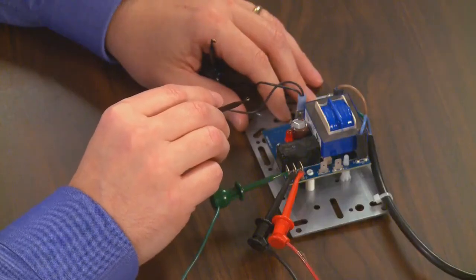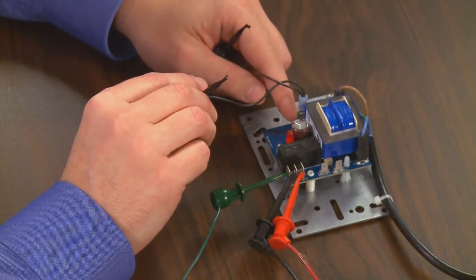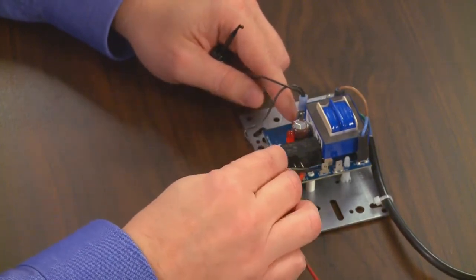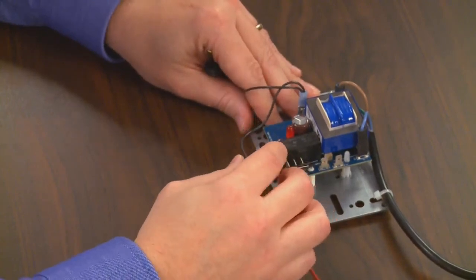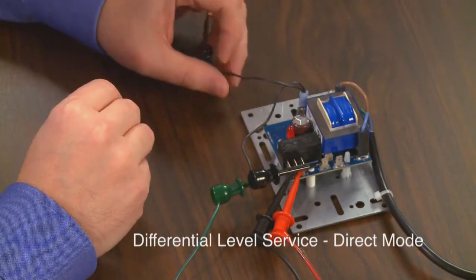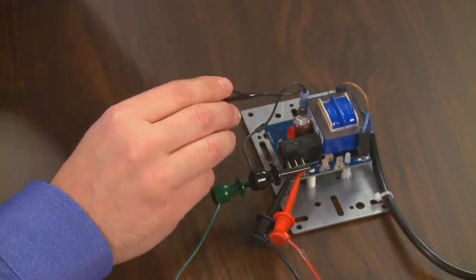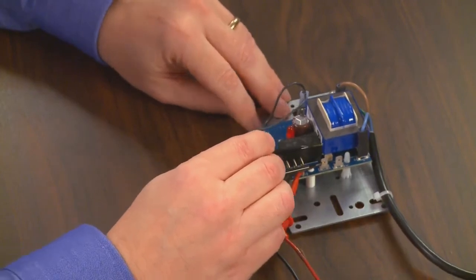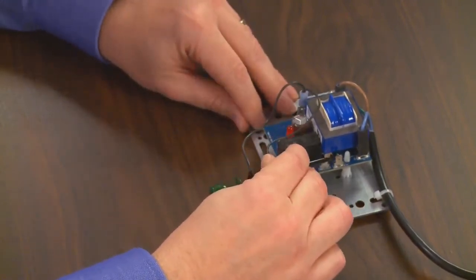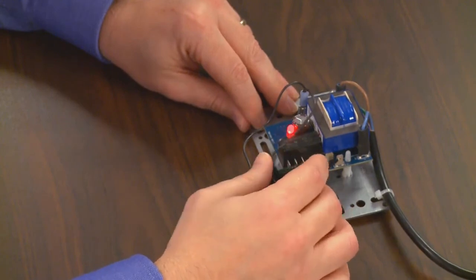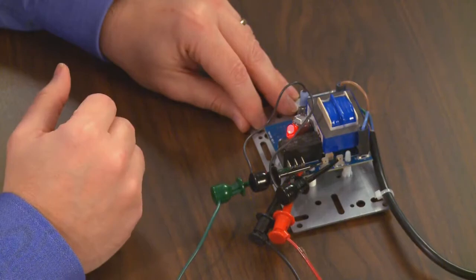Let's simulate differential service. We take our jumper wire from our ground reference probe to our low probe connection. As you see the LED remains off, meaning the relay is in its shelf state or de-energized state. As the water rises to the high probe, simulated by our jumper from the reference point to our high probe connection, you notice the LED turns on. The relay is now energized.